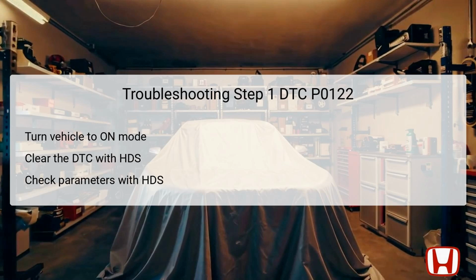It should be above 0.3 volts under normal circumstances. If the reading is less than this threshold, it indicates a confirmed fault, and you can proceed to the next troubleshooting step. However, if the value is not decreased, this indicates an intermittent issue, which may require examining connections or terminations.